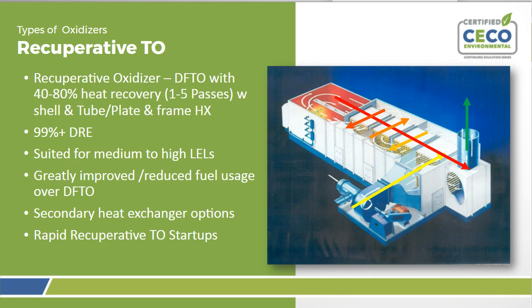This substantially reduces the fuel usage, as you recall from that graph earlier, but it is significantly more expensive than the DFTO because you have the tubes, the tube sheets, and the costly internal high temperature expansion joints, to make sure everything's happy at high temperature, as well as at ambient temperature when it cools down. So this is really the evolution of the DFTO. It's definitely been hugely popular in the past, but for the most part has been replaced by the RTO, the regenerative type, generally speaking.